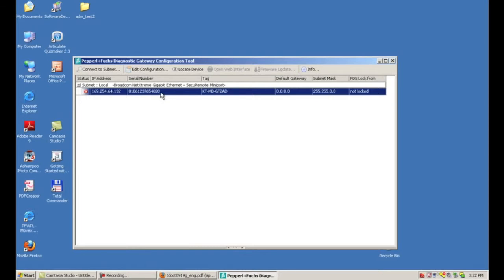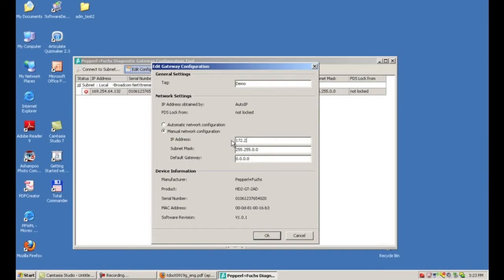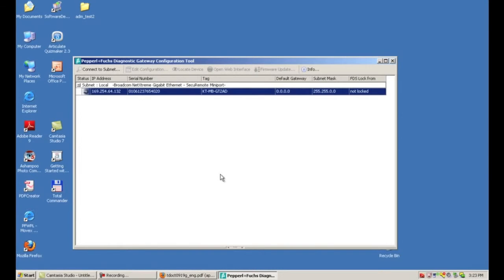It has a default IP address and a default tag. By clicking on the Edit Configuration button at the top, we bring up a screen where we can change the tag information — we'll just call that Demo — and if we click on this button we can enter an IP address. You can also use the Automatic Network Configuration to set the IP address, but you want to make sure that if you're using a DHCP server you always use a static IP address for the converter so there's no confusion and you don't have to change it every time.